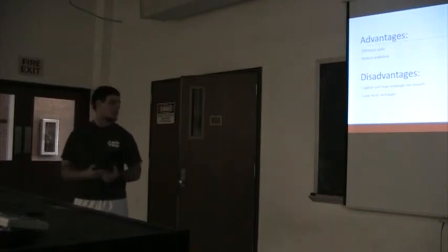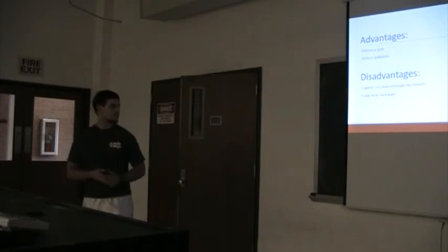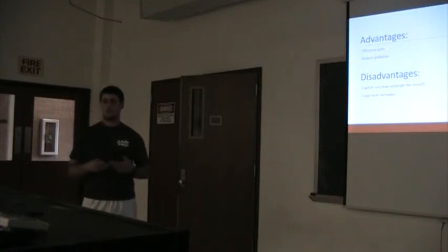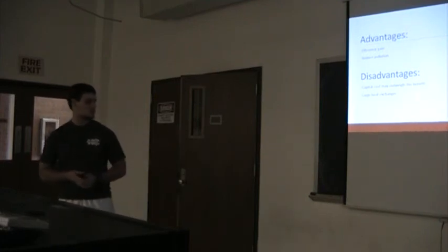Our advantage, obviously, we have an efficiency gain, and it also reduces pollution. You don't have to burn as much fuel to get whatever you need. Some disadvantages to this: capital costs may outweigh the benefit. The heat coming off of many systems isn't the highest quality, so you might have to use a very expensive heat exchanger just to get the heat from it to make it do something, and a large heat exchanger because there might not be so much heat.